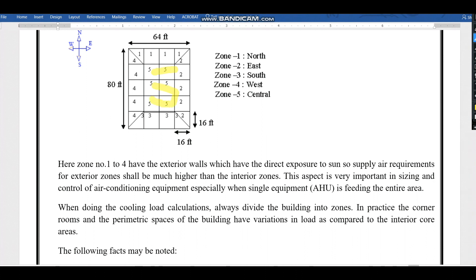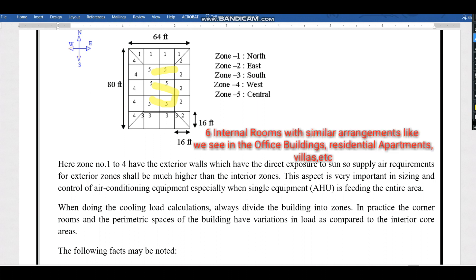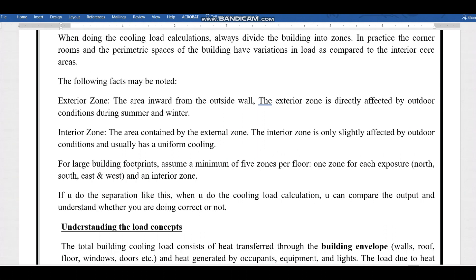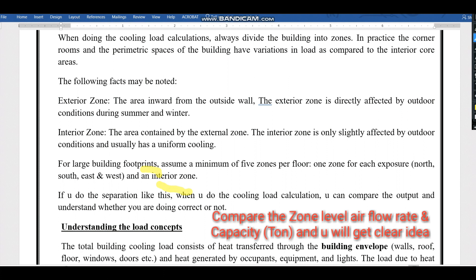For Zone 5 — the interior zone — if you have around six rooms with similar arrangements, the cooling load output will be almost equal. There won't be much flexibility in the output. But for exterior zones, the flexibility and output will be very different. For large building footprints, assume a minimum of five zones per floor: one zone for each exposure direction and one interior zone.